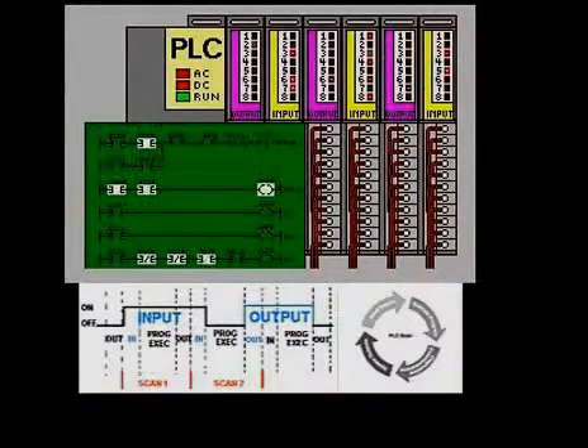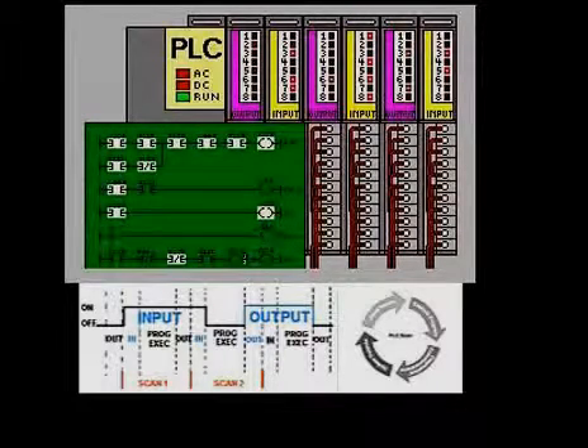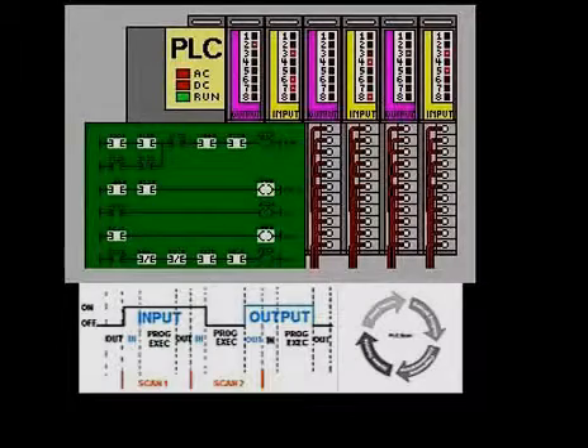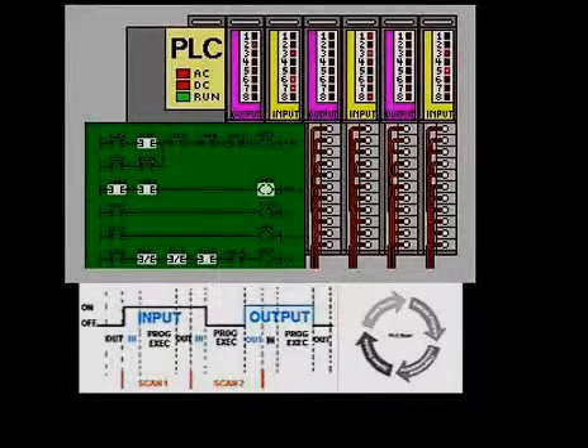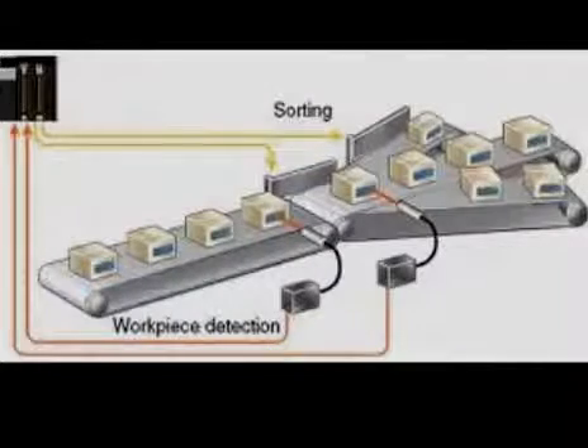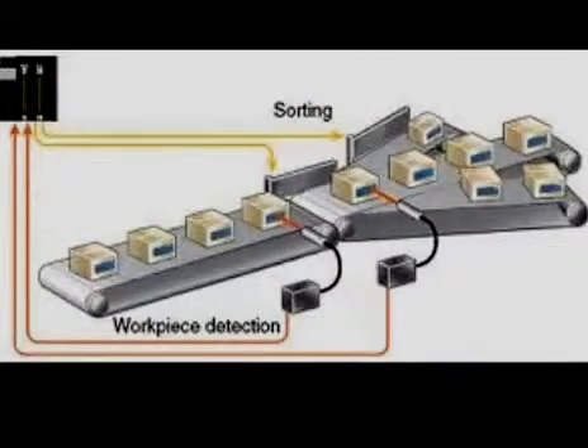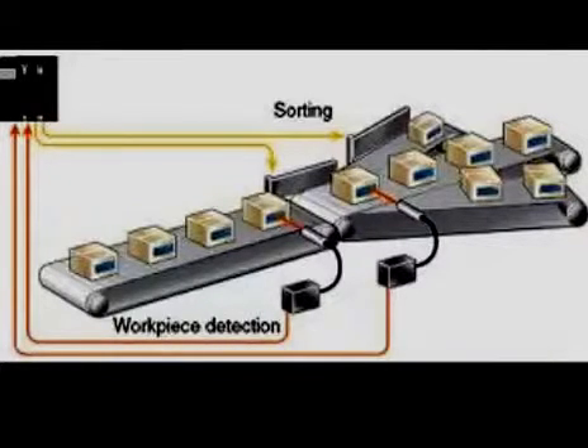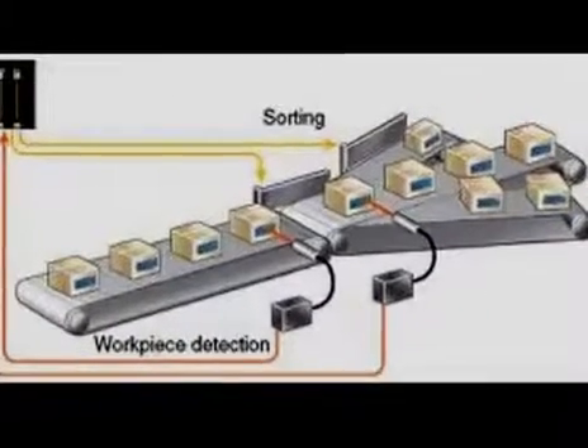The scan time may be a few milliseconds for a small program or on a fast processor, but older PLCs running very large programs could take much longer, say up to 100 milliseconds, to execute the program. If the scan time was too long, the response of the PLC to process conditions would be too slow to be useful. As PLCs became more advanced, methods were developed to change the sequence of ladder execution, and subroutines were implemented. This simplified programming could be used to save scan time for high-speed processes. For example, parts of the program used only for setting up the machine could be segregated from those parts required to operate at higher speed.